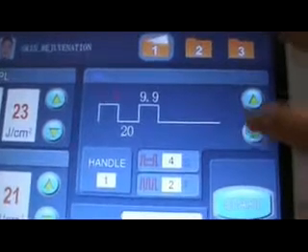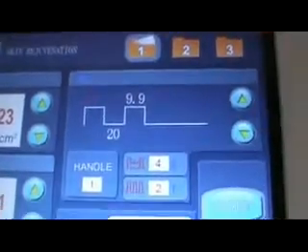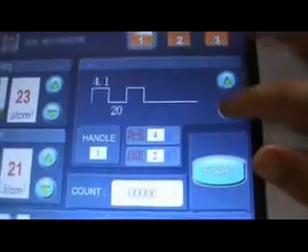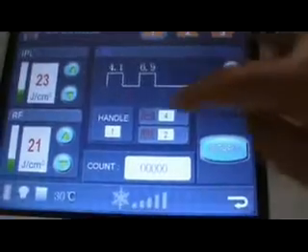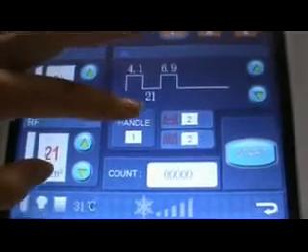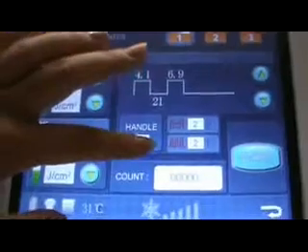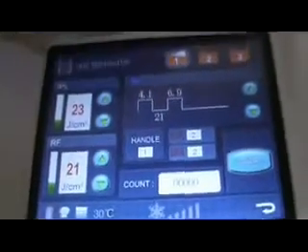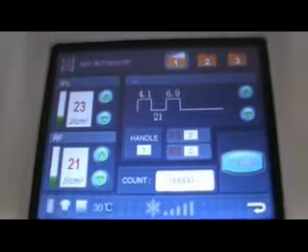This is the pause time. This is the second pause time. This is the pause delay time. This is the time for taking shots. It's set to two. It means you can take one shot every 2 seconds. And this is how many passes we need for this treatment. There are 3 fields in this place. You can keep different parameters for different patient situations.